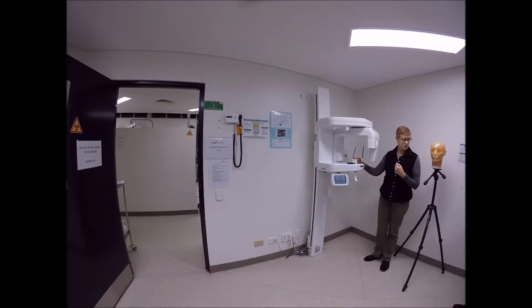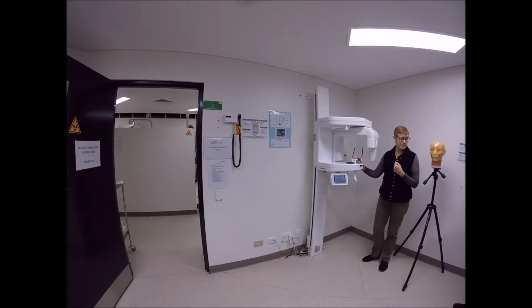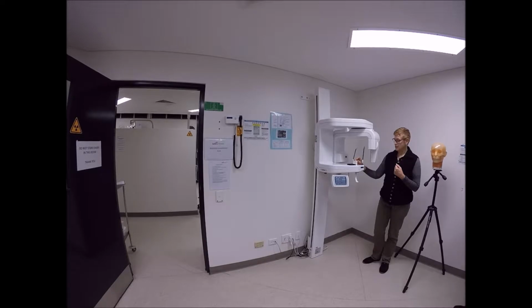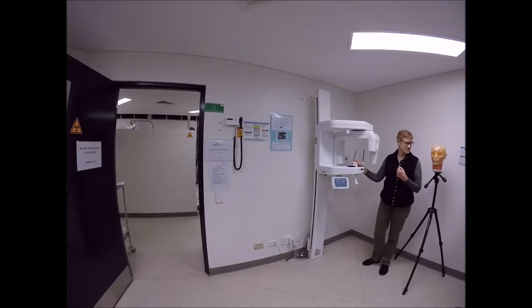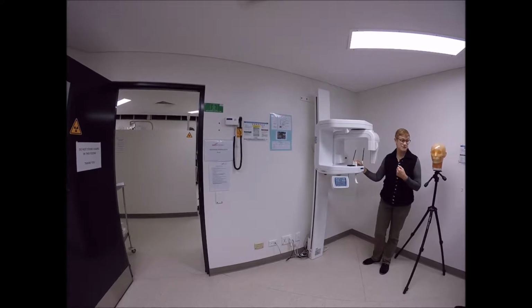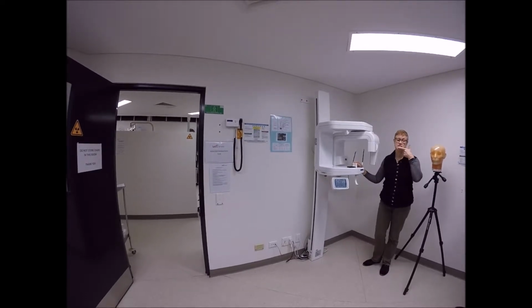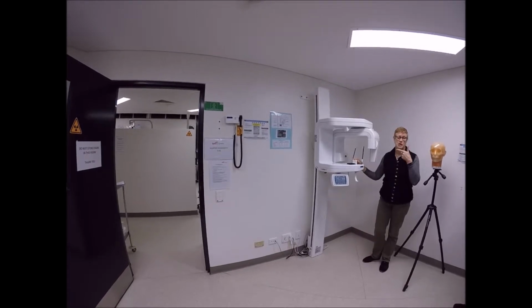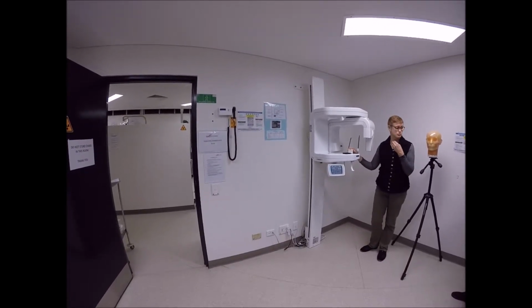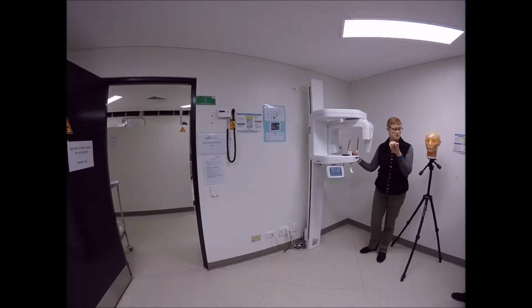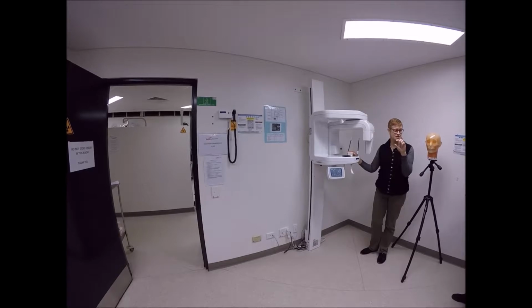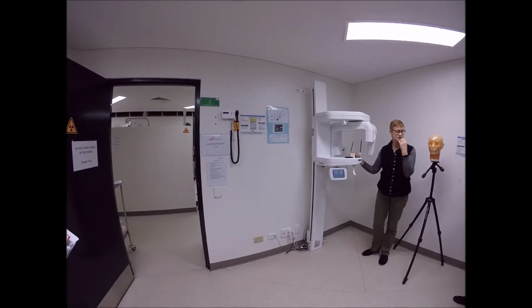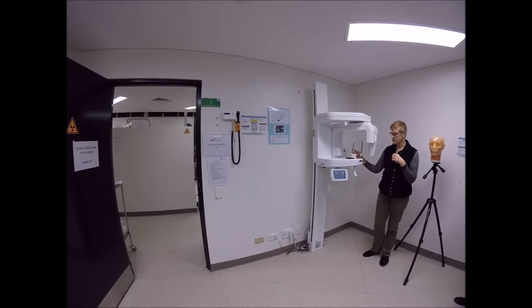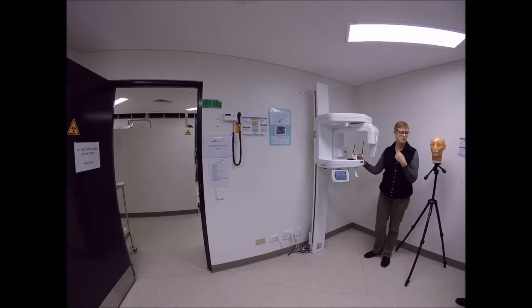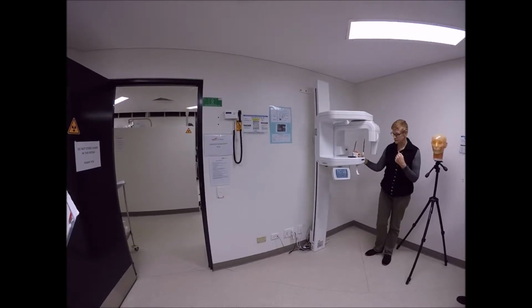This component here moves forward and back, and this is a chin rest, and we put a bite block in here. Some machines don't have the chin rest, they rely just on the bite block. All machines allow you to take the chin rest away and just put a support in, and people just rest their chin against the support. You might use that for someone who's edentulous, for someone who's had trauma and can't bite on the bite block. You could use that for someone who doesn't have any teeth that occlude in this anterior segment. So you can change chin rest and bite block, or bite block, to just a chin support.